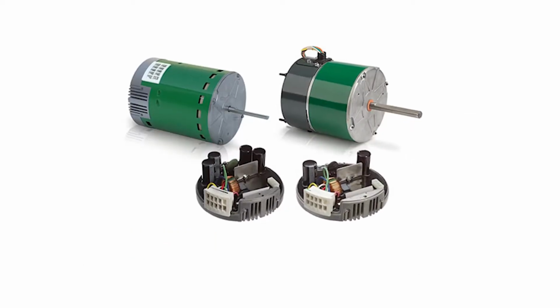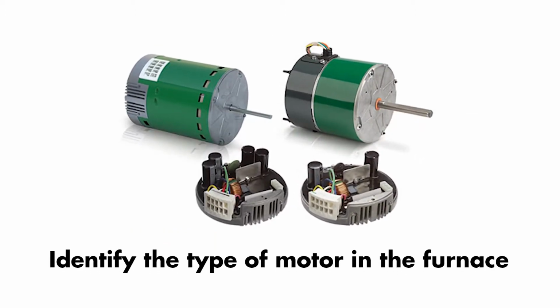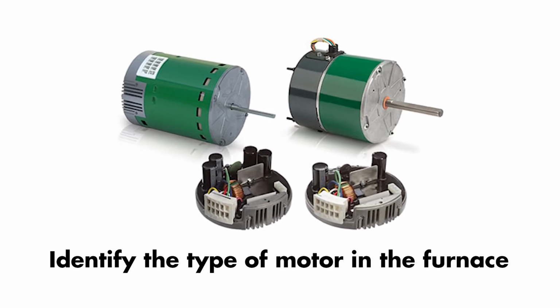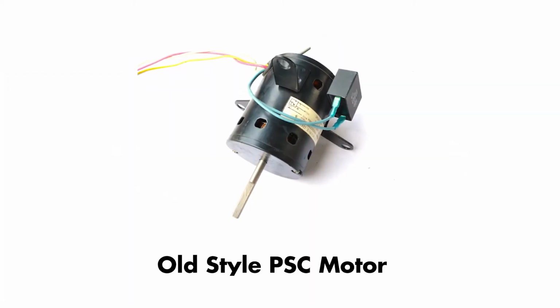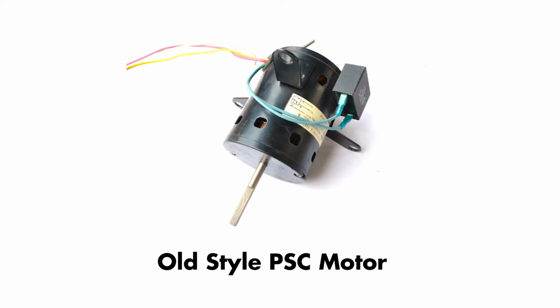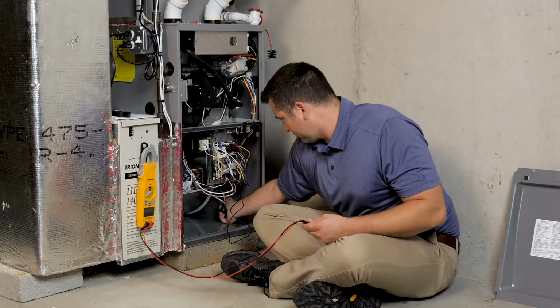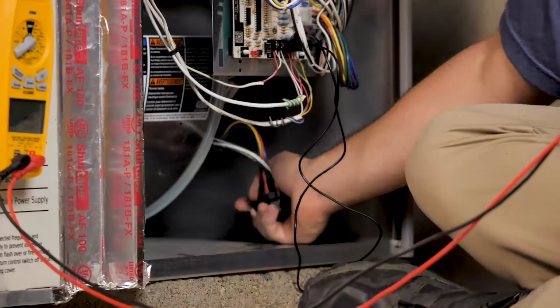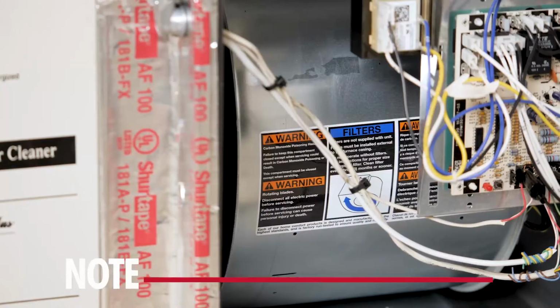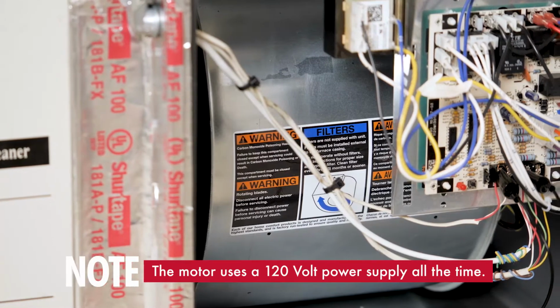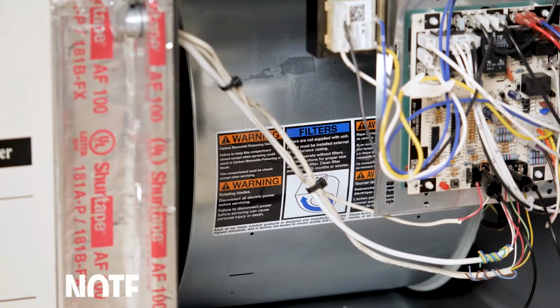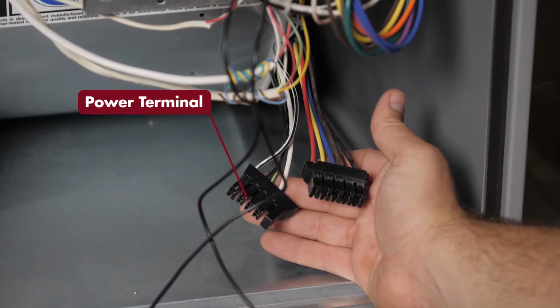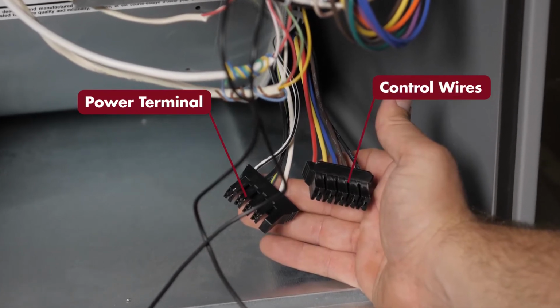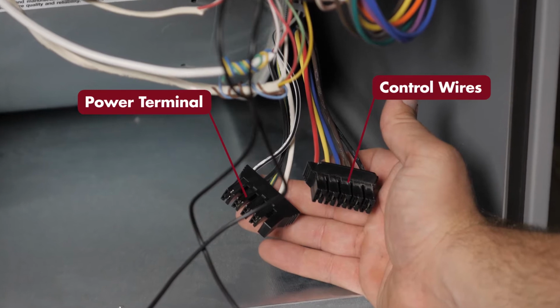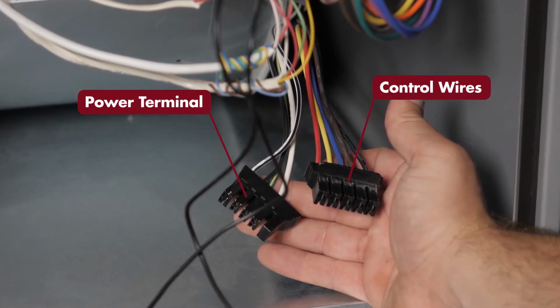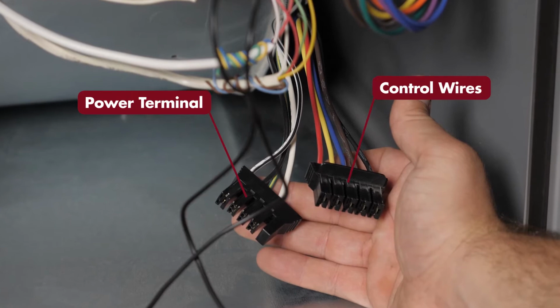Because there are two different types of motors, there are two different troubleshooting methods. You will have to be able to identify the type of motor. Also keep in mind that unlike PSC motors that have been the industry standard, both of these ECM motors are powered constantly. In the furnace, the motor uses a 120 volt power supply at all times. You will notice that both motors have one plug that provides the 120 volt line voltage. Another separate plug or set of wire terminals will be the control wires coming into the motor.